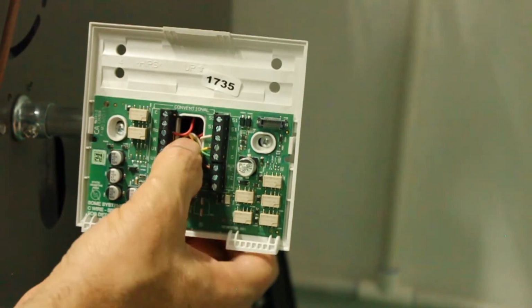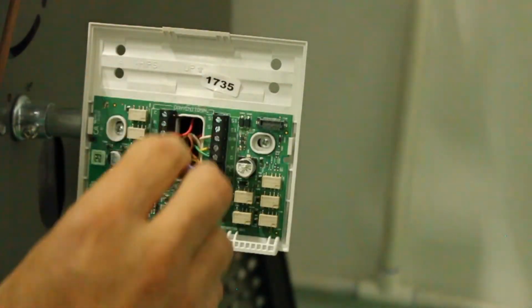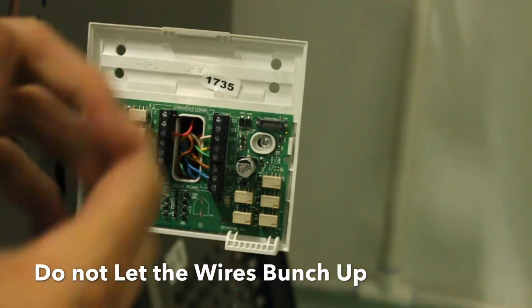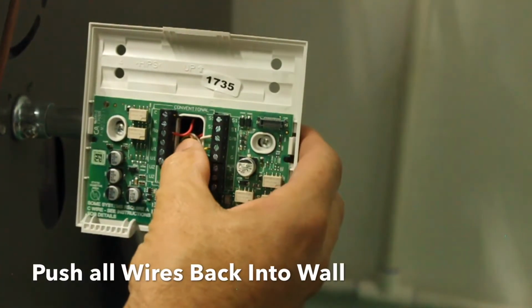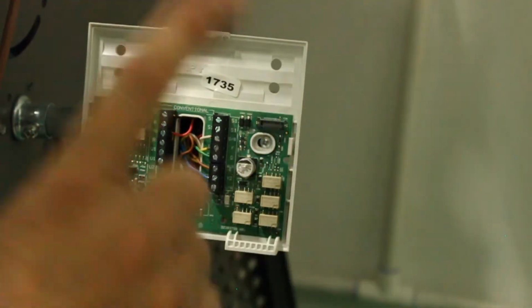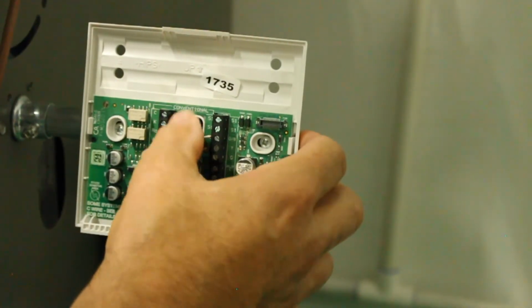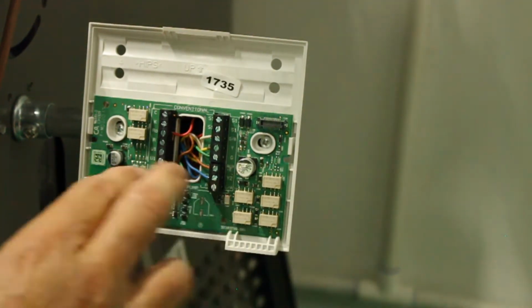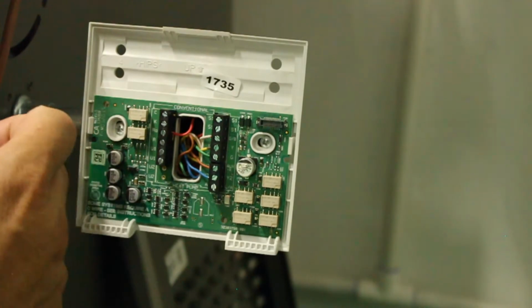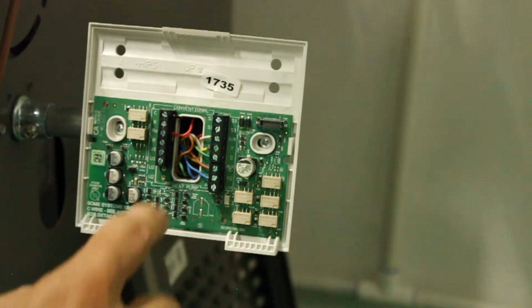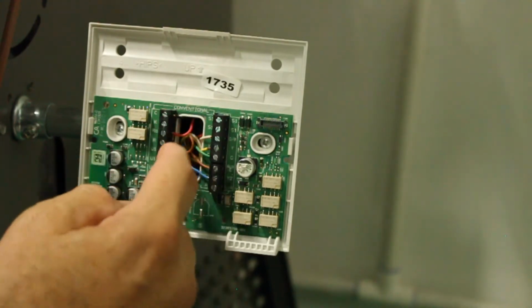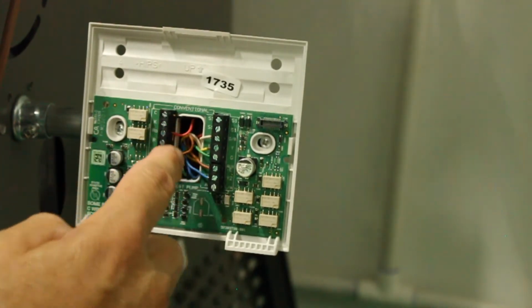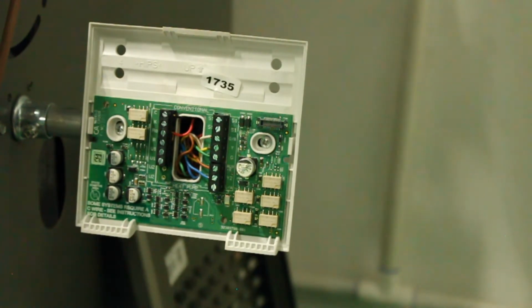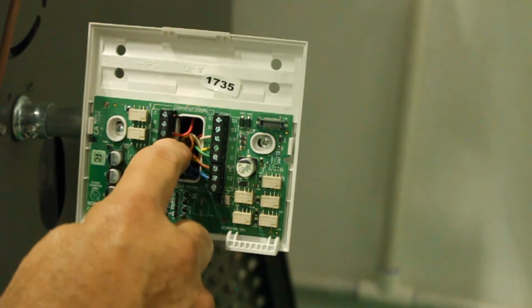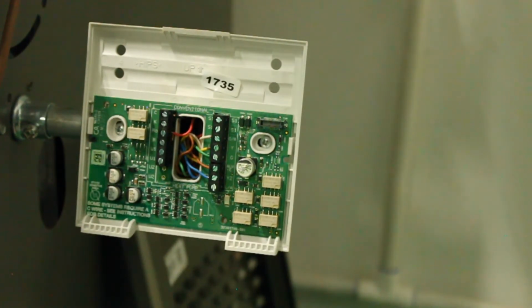Now when we place these wires back in the wall, or you take the thermostat, do not let the wires in the front jumble and crumble up. You want the wires to be nice and neat, and push them each back one at a time. Just do one wire at a time, place it in here, and then push it back. And if we have any excess wires, this could be a 7-wire thermostat cable, which is very desirable, because you say, Chuck, I only need 7. That could be 8, 9, or 10. I always like to pull a thermostat cable that has 1, 2, 3 extra wires, just in case one of these wires breaks. I have an extra wire without pulling an entirely new thermostat cable.